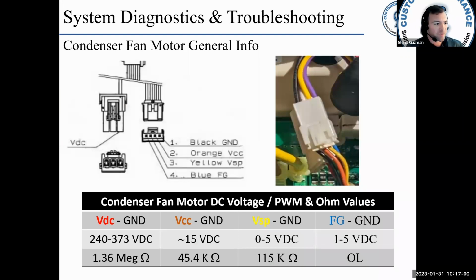Now, the fan motor winding resistance cannot be used because there are embedded electronics. So it's not like a PSC motor. You can't just ohm this thing out and say, well, the ohm values kind of make sense. They don't make sense. So we have this chart here. This is a DC voltage, pulse width modulation, and ohm values. If you look here, VDC, which is red, to ground. In this case, the black is the ground. So if I'm checking voltage between red and ground, I should have 240 to 373 volts DC.